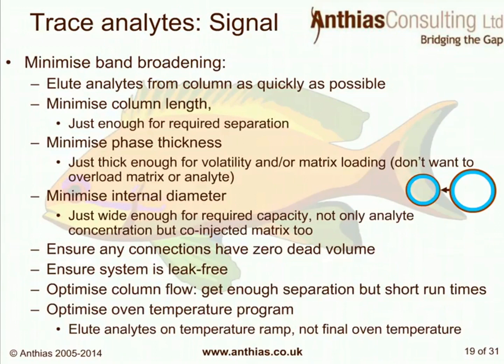To improve signal from trace analysis we also want to minimize band broadening — minimize longitudinal diffusion and elute analytes as quickly as possible. Minimize column length to just enough for the required separation; minimize phase thickness to just enough for the volatility and matrix loading; minimize internal diameter to just wide enough for the required capacity. Ensure connections such as between a pre-column and analytical column have zero dead volume, ensure the system is leak-free, optimize column flow for adequate separation but short run time, and optimize the oven temperature program to elute analytes on the ramp rather than the final hold.